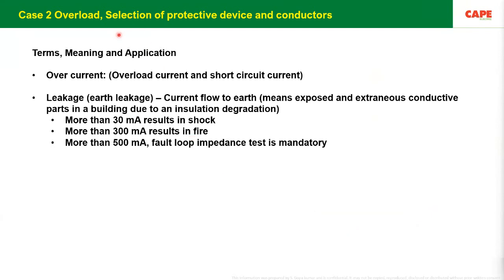Yeah, some of the terms with respect to overload, the terms for an electrical engineer. Whenever we say overcurrent, we should think that overcurrent is related to overload and short circuit. Overcurrent is related to overload current and short circuit current. Similarly, we call it earth leakage. Earth leakage means there is an insulation failure, a degradation in the insulation. As a result, a leakage current is flowing through the exposed and extraneous conductive parts. So here, what you should do is have a device, an RCD, with a tripping current of 30 milliampere, which is necessary to protect against shock. 300 milliampere is required to protect against fire, and if you have a device of less than 500 milliampere in your electrical installation, you don't need to test the fault loop impedance.